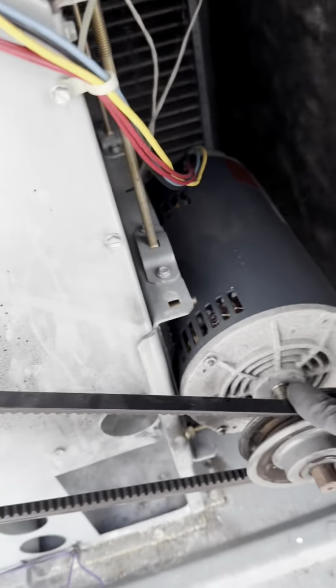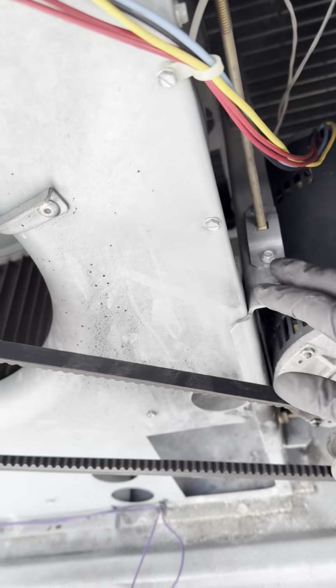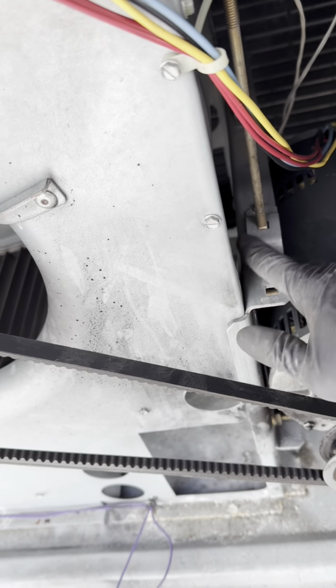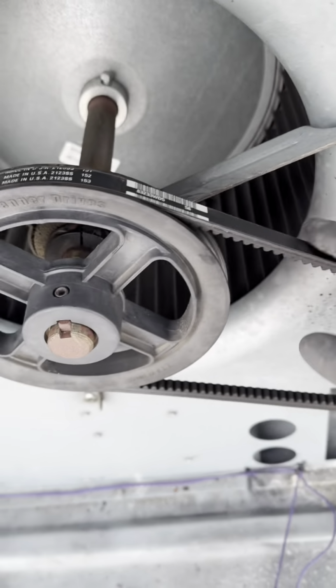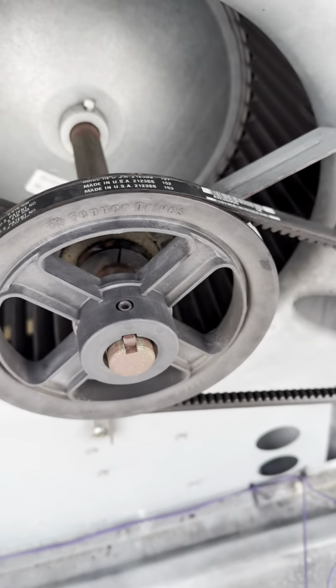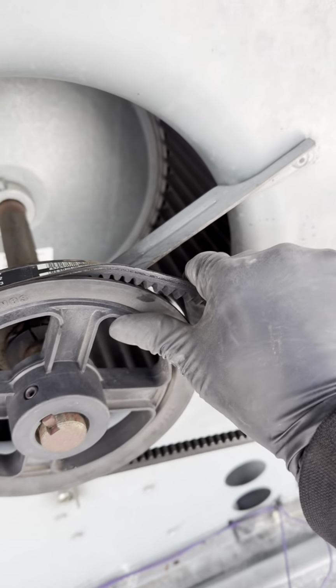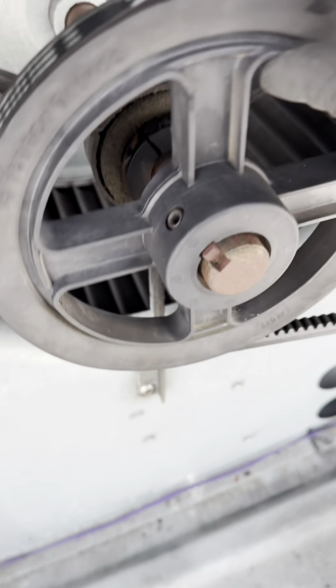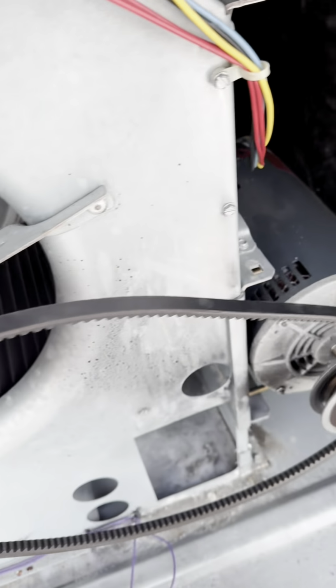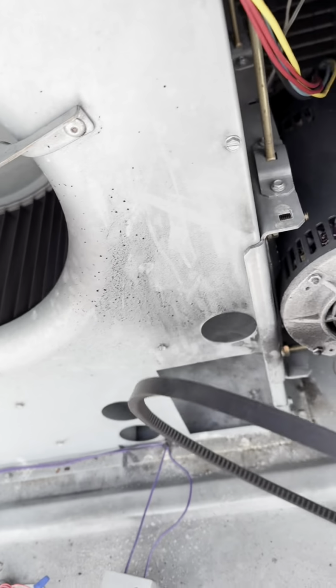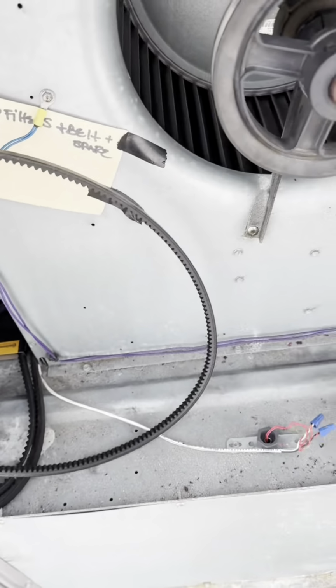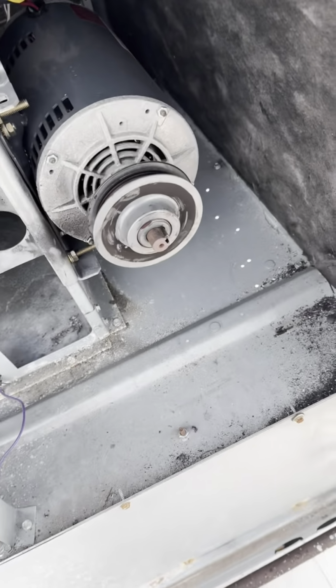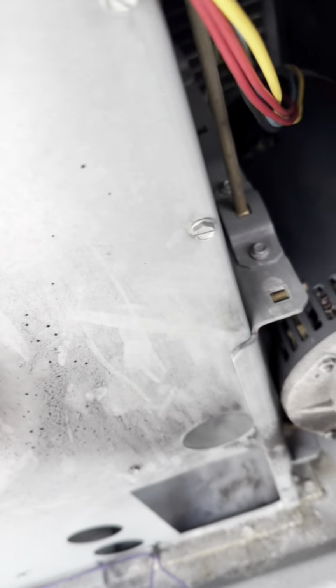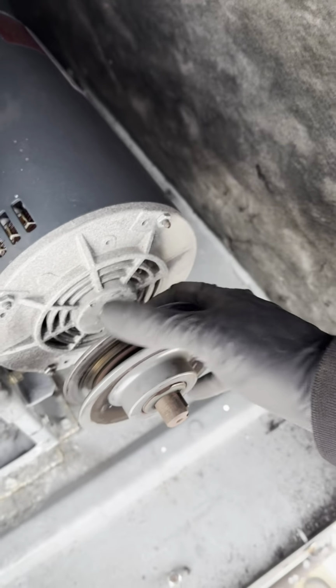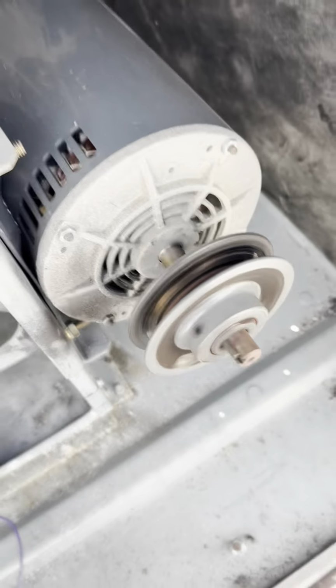First thing, we're gonna have to remove the belt. What you wanna do is periodically loosen the motor slack so that you can have slack on this belt and it'll come right off. But normally what I do is I just grab the belt like this and just go around and it'll slide right off. It's not recommended to do it that way because you could bend or break or warp something, but you just got to know what you're doing.